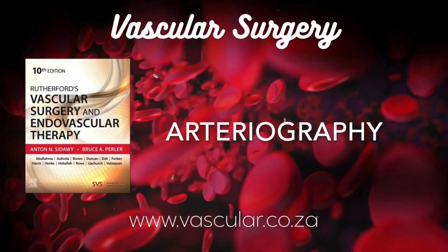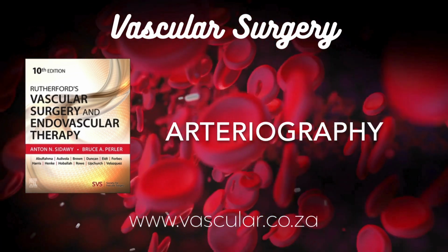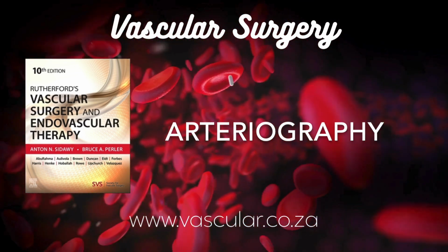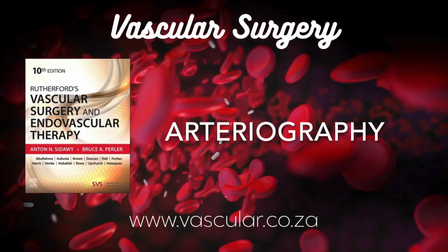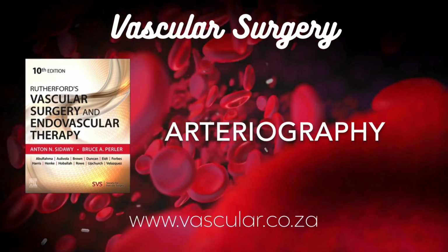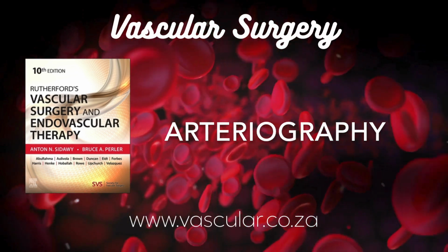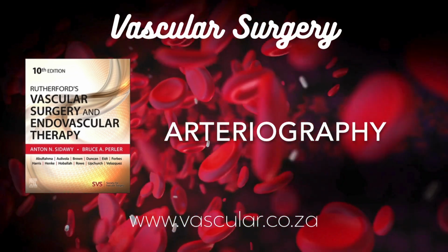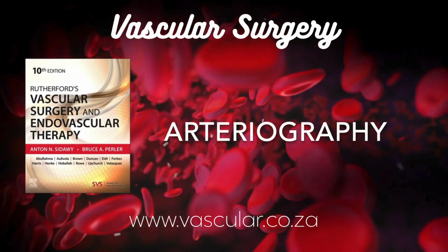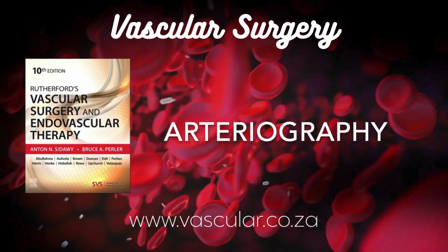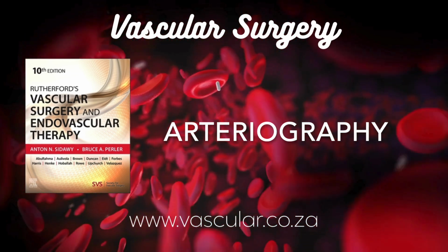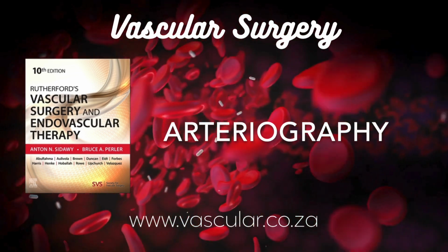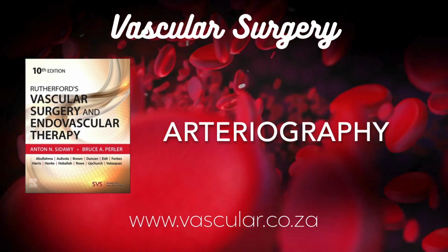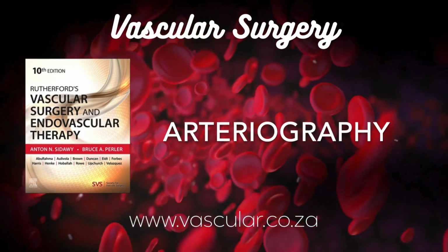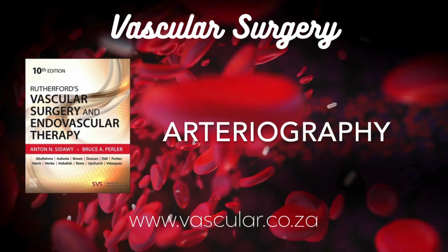I saw the term bolus chase, or single injection, multiple linear field arteriography. How does that work? Right, the bolus chase, it lets you image the arteries in both legs all the way down with just one injection of contrast up in the abdominal aorta. One shot for both legs. You need a wide image intensifier, usually over 15 inches, to see both legs. Then, after injecting the contrast bolus, the imaging system has to dynamically follow it as it flows down. There are two main ways to do this.